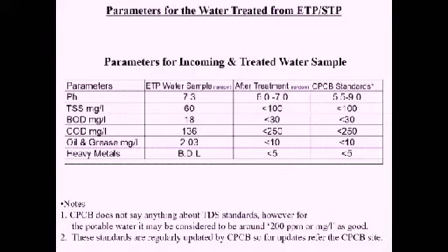Then BOD, in case the effluent or sewage water consists of bacteria or biological substance, is the biological oxygen demand. It is more in the untreated water, because the bacteria have to go through their life cycle before they become neutralized. So BOD is higher in the untreated water, but if it is less than 30, it is generally considered that the bacteria are neutralized in the water.